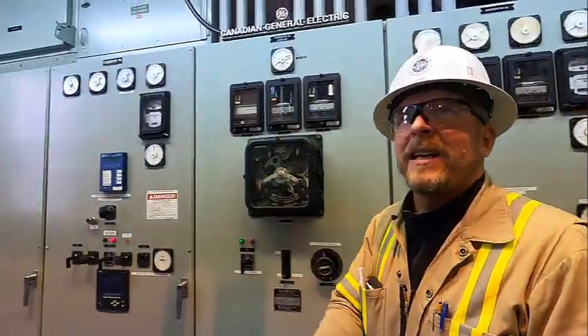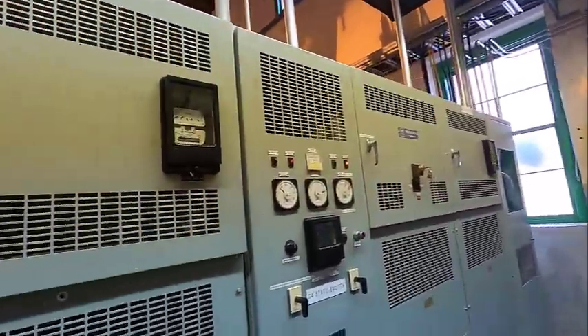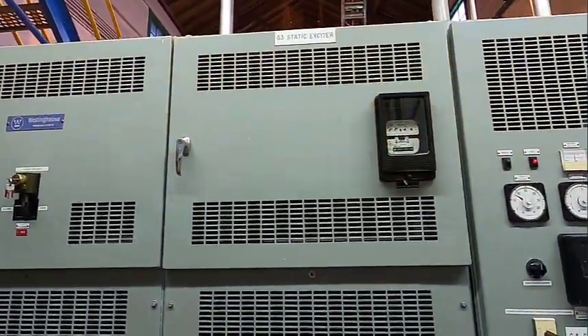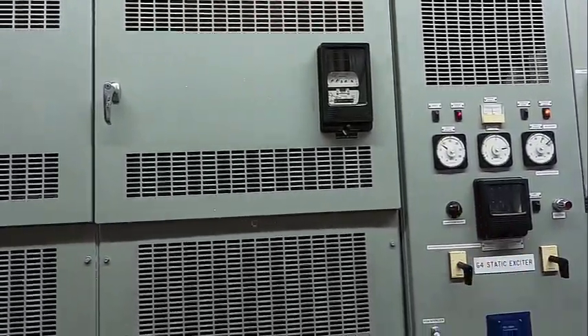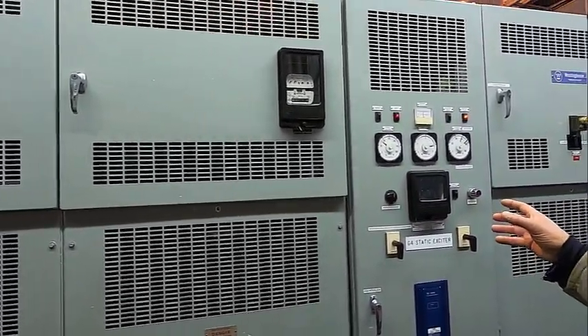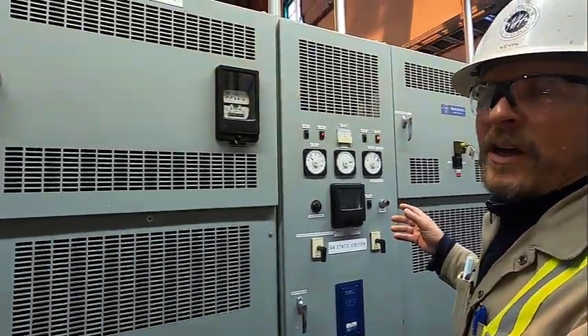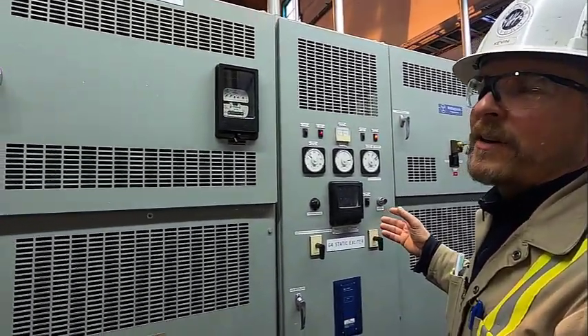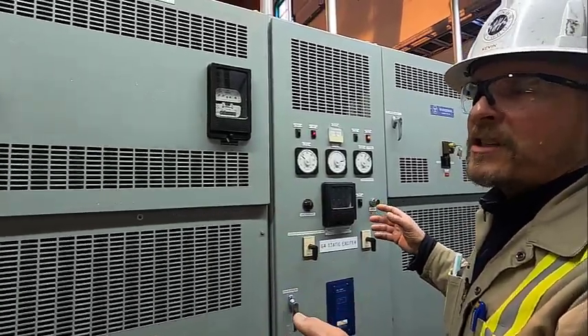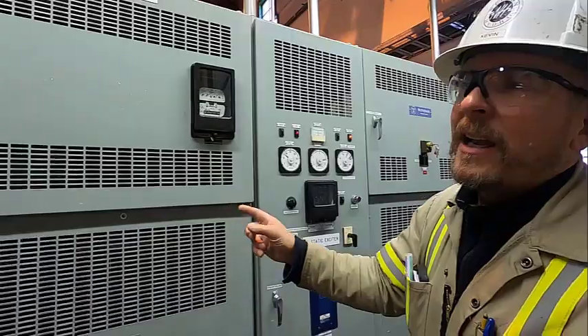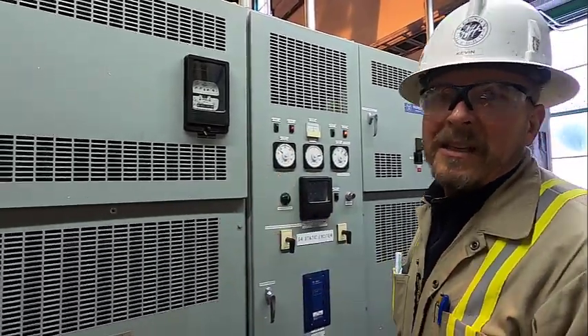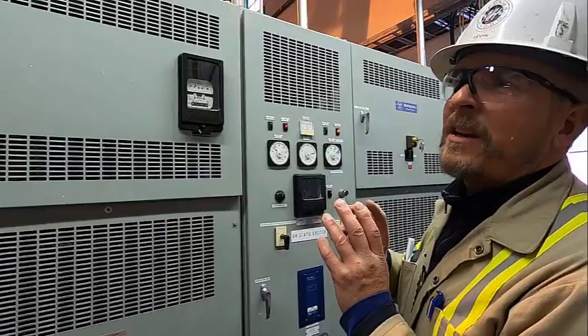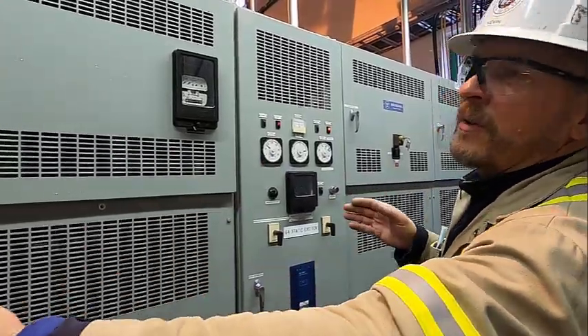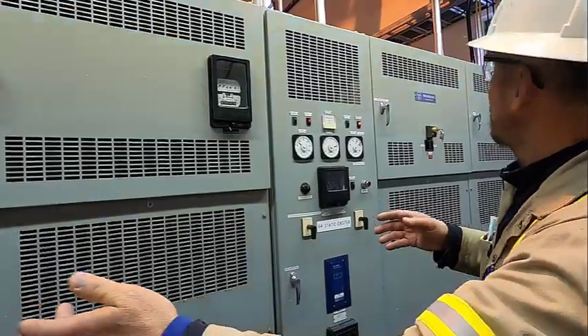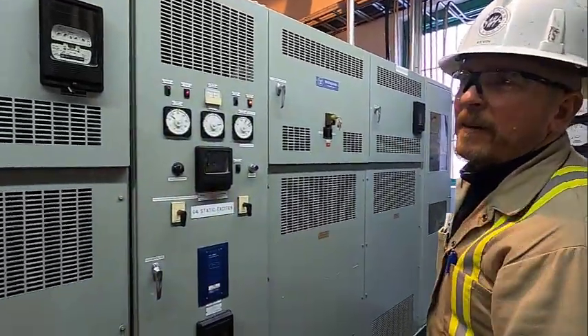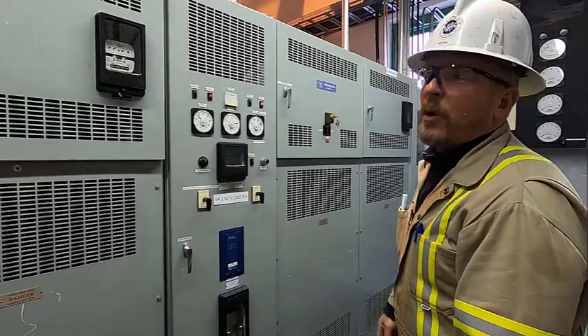Then right behind us here is what we call our static exciter. Unlike that oldest unit, 1 and 2 have a rotary exciter, these are actually just a large transformer that takes the 12,000 volts, the power that comes out of the generator, just a small portion of it, goes through a rectifier and creates DC power out of the AC power that comes out of the generator. That power is then fed back into the rotor of each unit. So right here is our unit 3 exciter, and then this is our unit 4 exciter. It's just a little bit different process of doing the same thing.